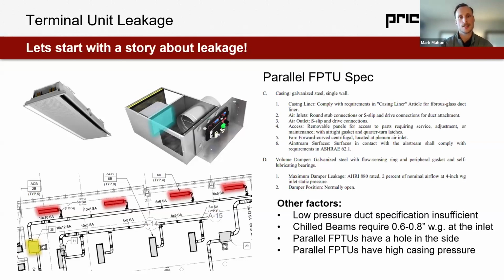They're using a fan powered box in a parallel orientation, which we can see in yellow in the bottom left, and then we can see a render of it on the screen. This product has a huge hole in the side and is generally used in low pressure applications. But in this case, we're seeing about 1.2 inches of downstream static pressure for the terminal. And a big hole in the side means leakage out the side of the product. When we look at the spec, which is in the top right for this product, there's no casing leakage specified whatsoever. There's damper leakage, but no casing leakage.